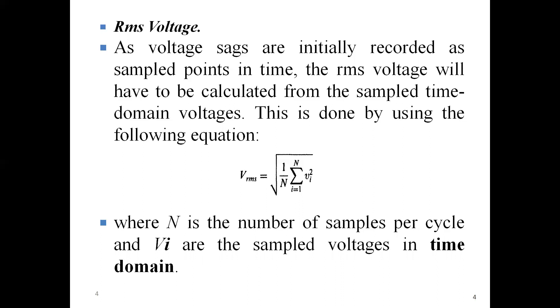These monitors record voltage in different timings through sampling — not continuously. For one cycle, 256 sample voltage values are collected or monitored, whereas for half a cycle, 128 samples are recorded. So N is the total number of samples per cycle, and V_i is the sampled voltage in time domain. The difference here is that instead of integrating over a duration T_s, we calculate over the total number of samples, integrating over each sample, because we are interested in calculating the voltage sag per duration.